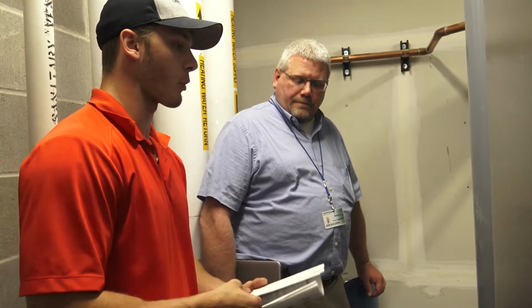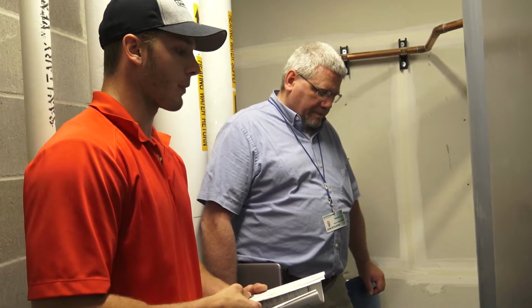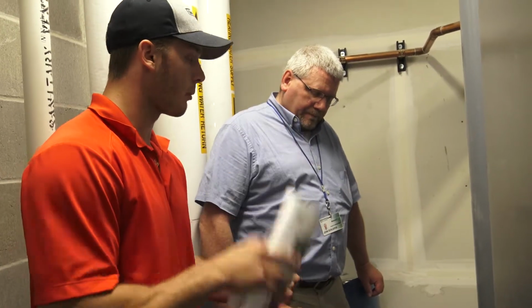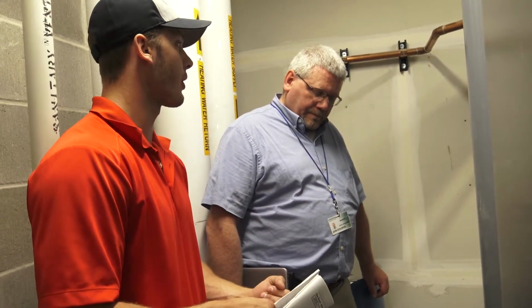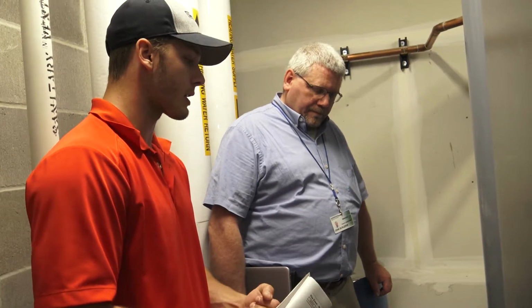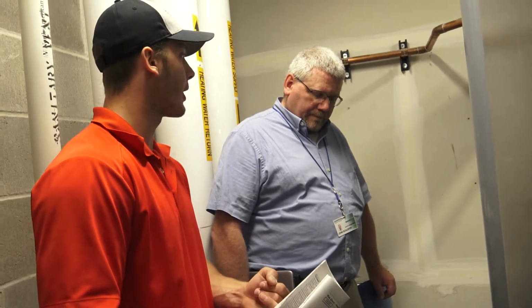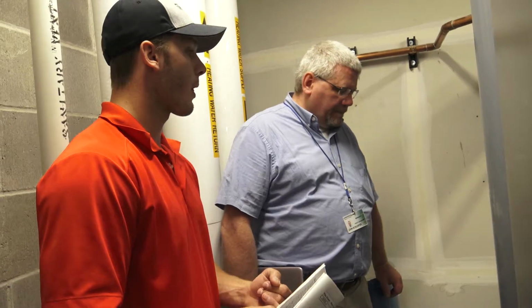And I suppose it's normally a year that you'd run that at. Since this thing isn't going to run very often, would it still be a yearly thing, or could it go out further than that? It could potentially go farther than that. I guess you could base it off of runtime hours. Definitely combustion analysis once a year, every winter, before every heating season. I would be having somebody come in and do combustion analysis.